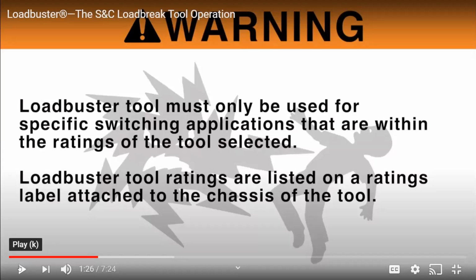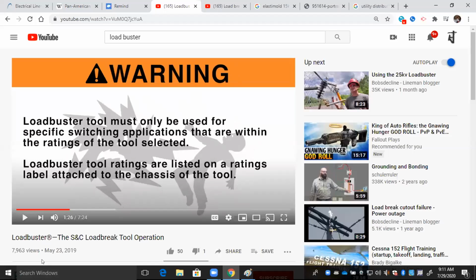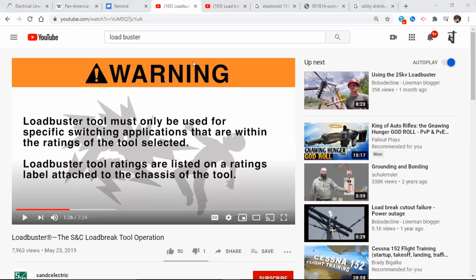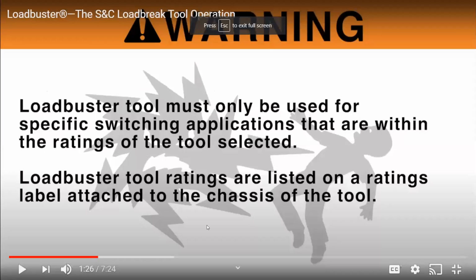Okay, so you've got to watch out for 2 ratings on the tool. One of them is the maximum voltage that's allowed for the tool to be used on, and typically they come in 20 kV and 40 kV tools. So you're able to use the tool up to 20 kV or up to 40 kV, and there's also an amperage value. They have 2 different units, and the cost between those 2 units is substantial. There's a 200 amp and a 300 amp tool.